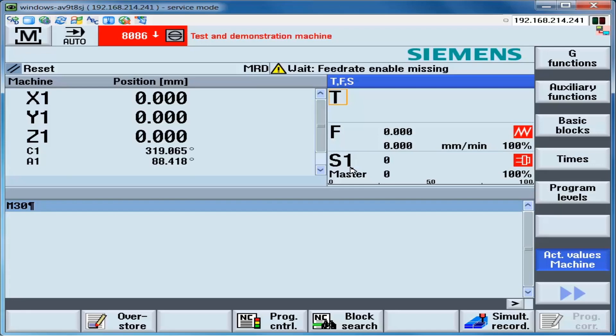The process for these cases is such that each time the drive is powered off and back on, the coarse pole angle is determined by the relevant pole position algorithm. This is close enough to allow the motor to rotate under control. When the motor rotates and sees the reference pulse from the encoder for the first time, the drive switches to fine synchronization and uses the value in P431 for synchronism via the reference pulse.